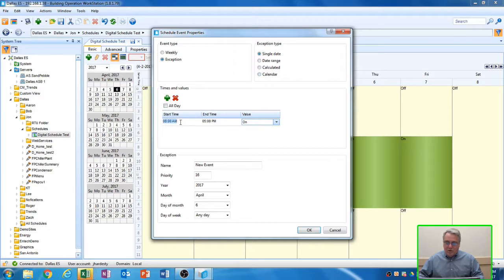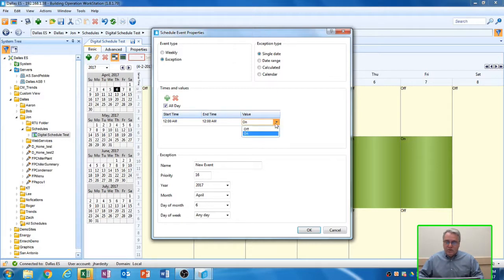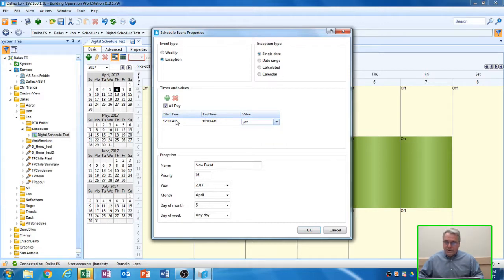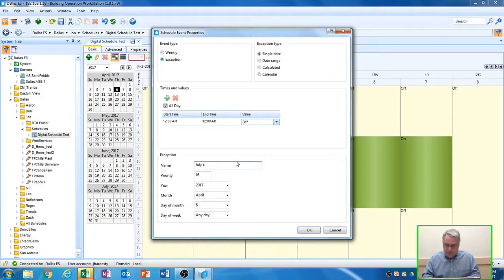We want to put our start and stop times on here. In this case, we want the unit to be off all day long, so I'm going to select all day. And it automatically fills in 12 a.m. to 12 midnight. Don't forget to change your value of what you want the schedule to do during this time period. We want the schedule to be off all day long. Down at the bottom of the screen, we want to name this event. I'm going to call it July 4th.